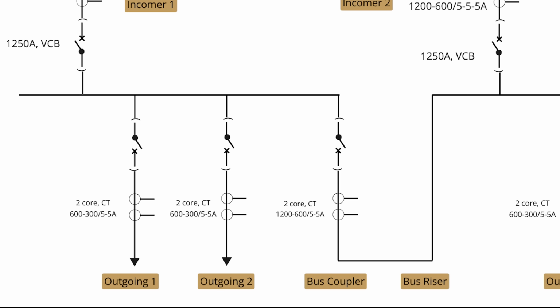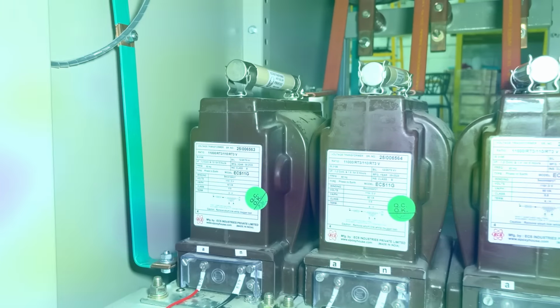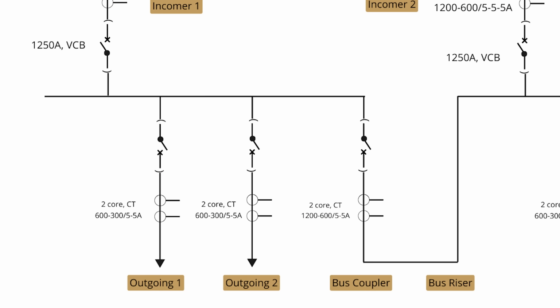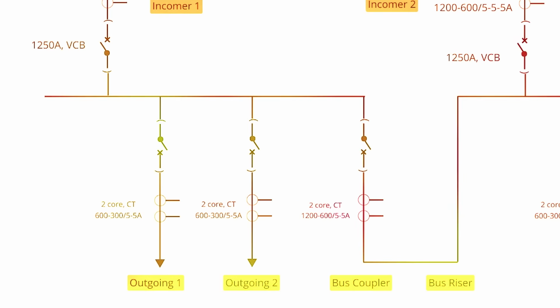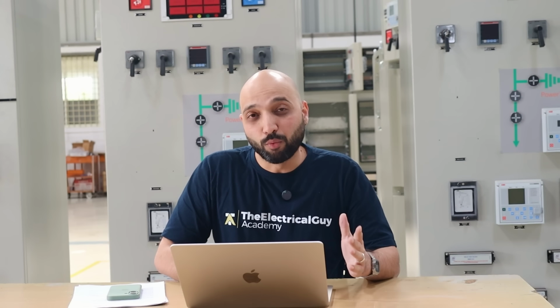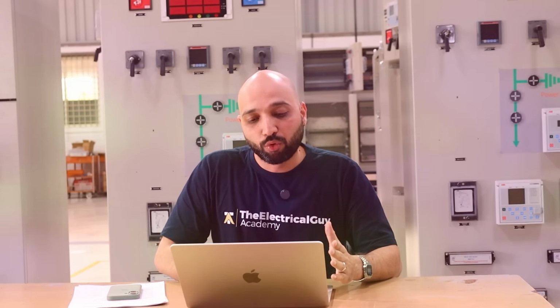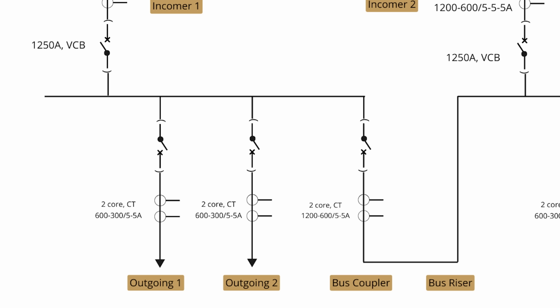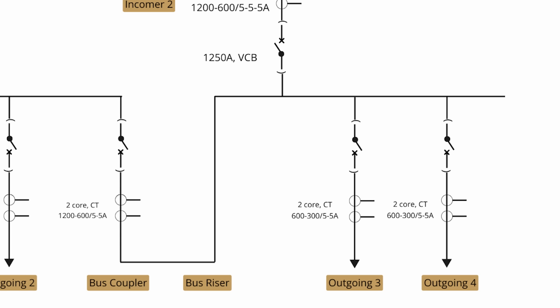So this can be used for protection purpose or maybe metering purpose. We are not using any PT here. It's not needed as well because we are taking the inputs from the VT that we have on the incomer side. So that's why the VT is eliminated here. And that's all we have in outgoing 1. Same way you can see the outgoing 2 is identical. So both these panels are identical. In fact, if you look at outgoing 3 and 4 as well, all those outgoings are identical.